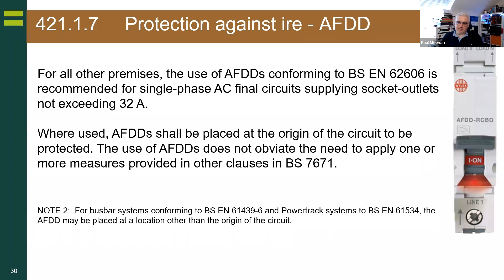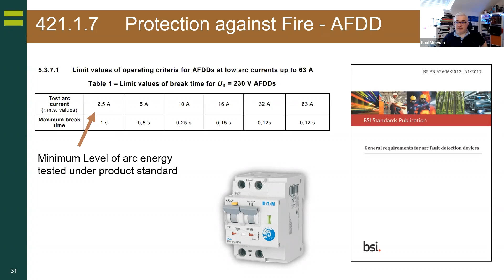There's a bit of controversy as to whether they will trip or not. In the standard itself, 62606, they're tested to a minimum value of 2.5 amps. That's not to say they won't work under 2.5 amps, but the magnitude of current needed to form a stable arc has been defined from testing as 2.5 amps, and they guarantee a trip time of 1 second. Below 2.5 amps, it's not to say the device won't trip, but it may be a trip from earth leakage rather than the AFDD component. That's directly from the 62606 standard.